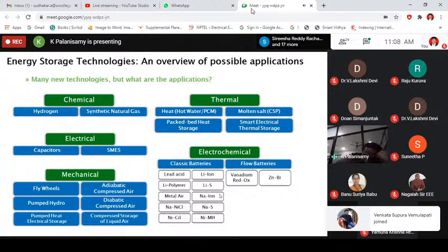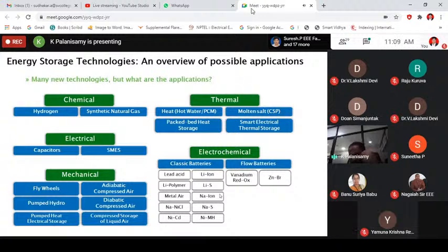But those batteries can be given to a grid operator, so they will use those batteries to store, right? When there is a high random variation, then they will use lithium ion or this kind of batteries. So here, see, we need not worry about the loss of the rating or loss of the energy density, right? We can handle it because the number of energy backup events will be somewhat less. So you can use the old batteries for your grid support services, right?